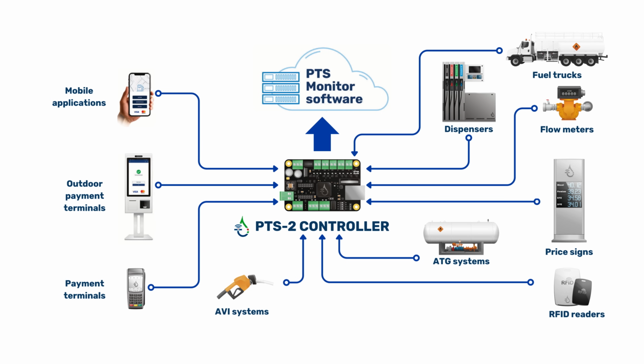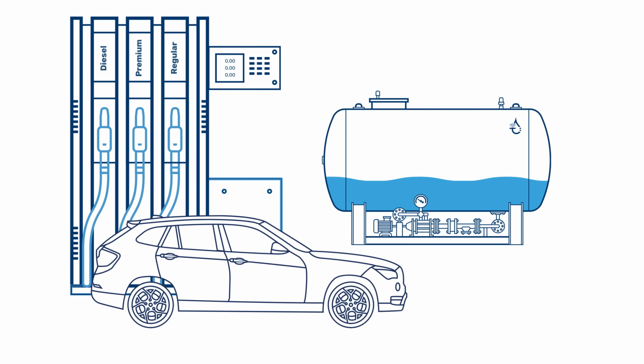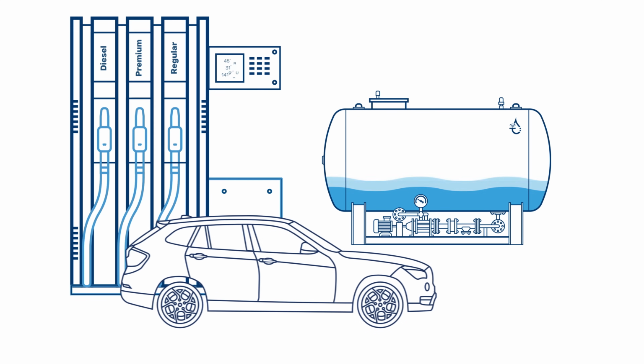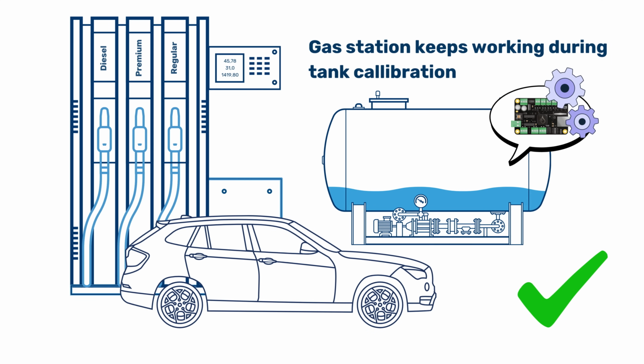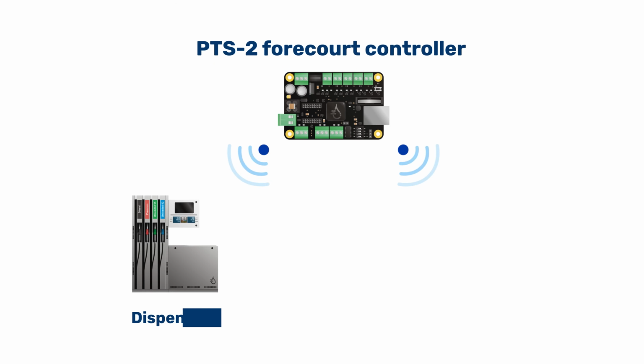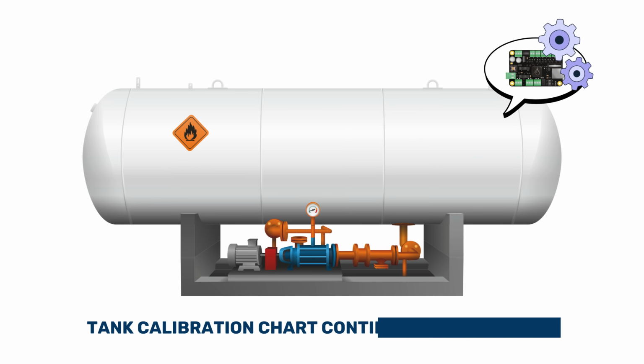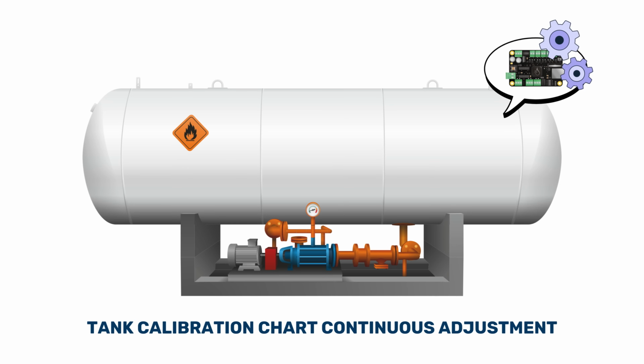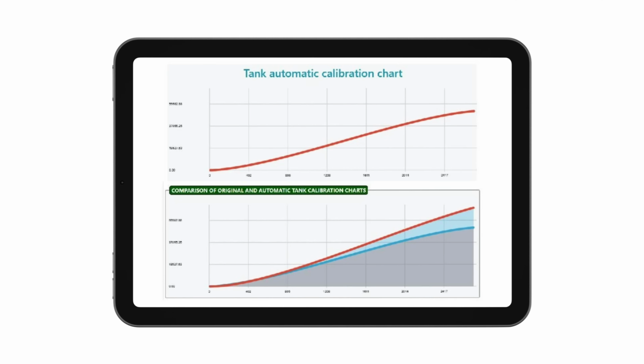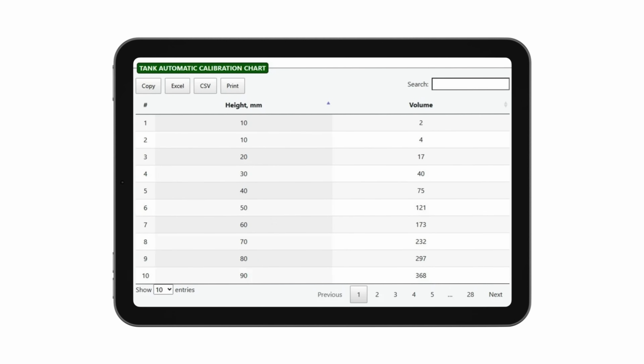The PTS2 forecourt controller is able to perform automatic tank calibration without stopping the petrol station operation. Each tank's calibration chart is automatically calculated and adjusted through the tank operations. For this process, the PTS2 forecourt controller communicates with both the pumps and ATG probes installed inside the tanks. As the result of this process, the PTS2 forecourt controller forms and constantly adjusts the accurate calibration charts for each of the tanks, which suit their actual state and which are used for precise calculation of the fuel volume remaining in tanks, in tank deliveries registration, temperature compensated volume calculation, and other technological processes.